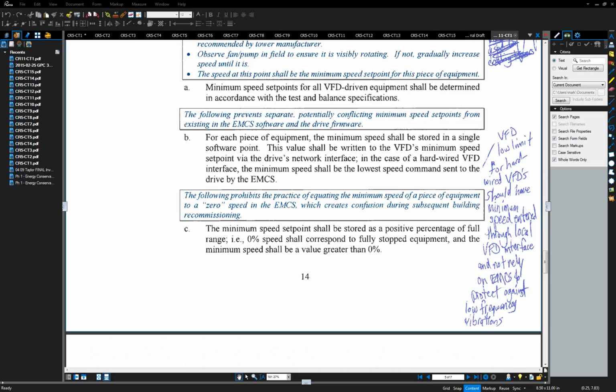So if you look at all these sequences, they're all demand-based resets on supply pressure, for instance, and also when we get to the wet side, which is not part of this document yet, we'll do that with head pressure control. But for fans and pumps, if it's a reset set point by demand, there is really no issue of going as low as you can go, the slowest that keeps the pump or the fan turning. Of course, once you get down to about 5%, there's almost no energy there anyway. And we've talked to motor manufacturers, Baldor, U.S. Motors, others, and we've talked to the drive manufacturers, ABB and others, and we've done black box radiation models to show that there's no real energy there.